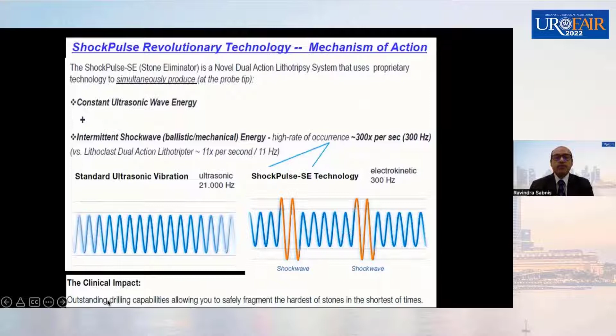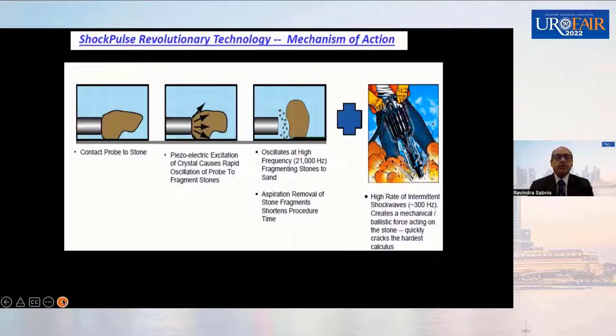Now, how does it break the stone? When the probe comes in contact with the stone, the piezoelectric excitation of a crystal causes rapid oscillation of the probe to fragment the stone. Whatever fragments and powder are formed at the 21,000 hertz frequency, that powder is effectively sucked out and the fragments are removed effectively. And in between, at 300 hertz, the energy developed from the ballistic creates cracks in the stone, and that enhances effectivity further. So it is a very effective combination from the point of view of breakage of the stone.